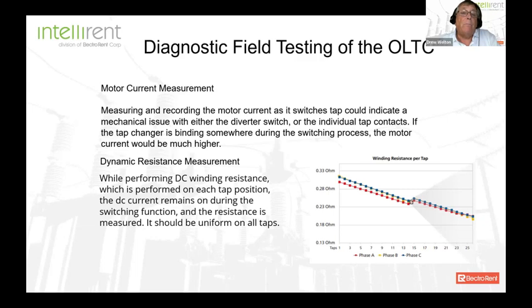The other thing we can do is measure the motor current of the LTC. If you have any contacts there that are binding, that's going to drive the current of the motor turning the tap changer to be higher. Now, the other one that people are really paying attention to is what we call dynamic resistance measurement. While you're performing your DC winding resistance, instead of turning off the DC between each one of the tap movements, you keep it in place, and then you look at the transient and record the transient current as it goes from one tap to the next. They should all be uniform. If not, then you probably have a problem.